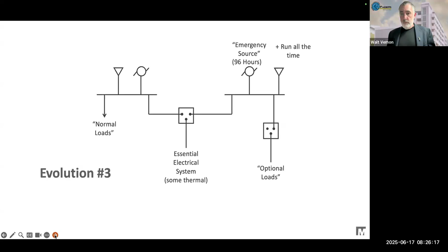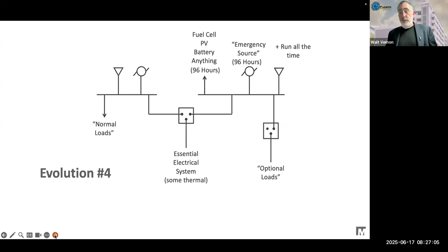Then we said, okay, now we're going to open the door to more than just diesels, and allow hospitals to put fuel cells, PV, batteries, microgrids—basically anything—as a source of power on the emergency side of the equation. You could already do that on the normal side. So all we've really done is expand it so you can have anything you want on either side of the transfer switch, they can all run all the time, and they can all serve any load you want. The main distinction is we wanted to make sure we had 96 hours of on-site capacity so that if everything else failed, we could keep the hospital operating for 96 hours.